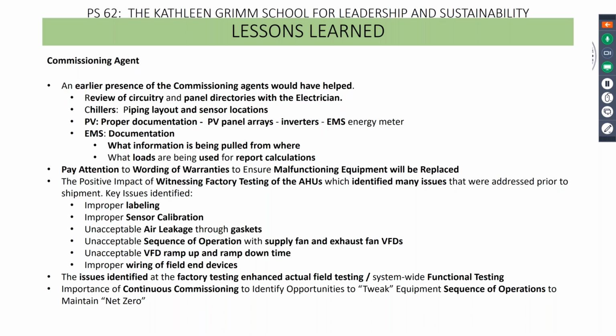What we're actually happy about now is the evolution in the industry, where we can put in more localized CO2 sensors that are much more accurate than they were at the time this was designed, in 2013. So we don't have to go to a whole building type system like that, but just have a CO2 sensor operating an in-room damper that can damper things down and send feedback back to the main units.